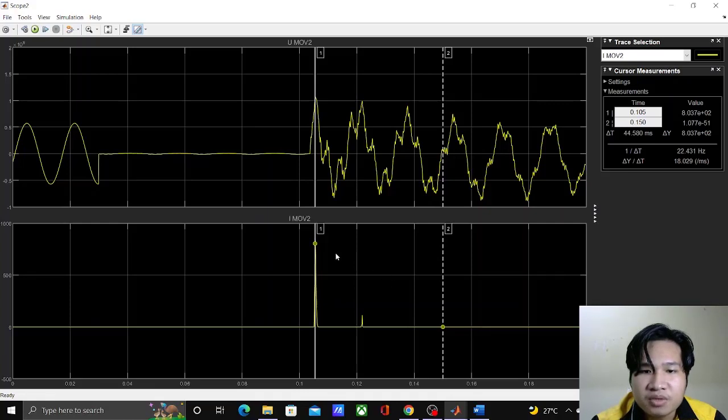When the fault is applied, we can see an impulse graph which at peak is 803.7 A. So we can see that the current is conducted by the surge protector device to protect our inductor from overvoltages. That is all for Task 1.